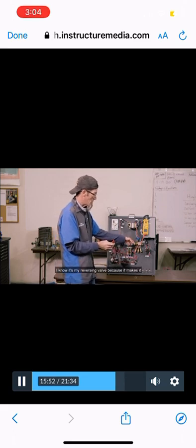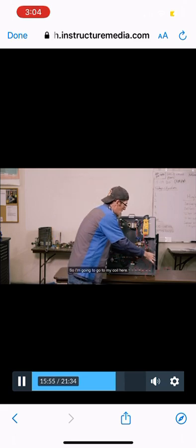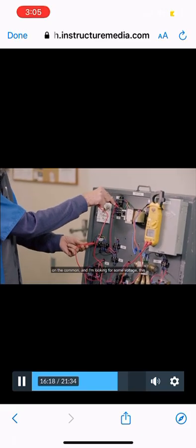Again, everything's on. I know it's my reversing valve because it makes a really screaming noise. So I'm going to go to my coil here. We should have some voltage. I don't have anything. So I'm looking at who tells that coil what to do, which again we talked about earlier is going to be this blue wire, even though it's connected to the O. So I want to find out, do I have power coming from my thermostat? So one hand on the blue wire, one hand on the common, and I'm looking for some voltage. This particular one I have voltage, which means my thermostat is sending the power in. So now there's a wire that goes from right here to here, and there's a wire that goes from this side back up to this common. Kind of makes a complete circle or a complete circuit.